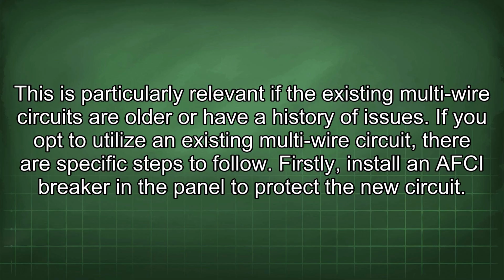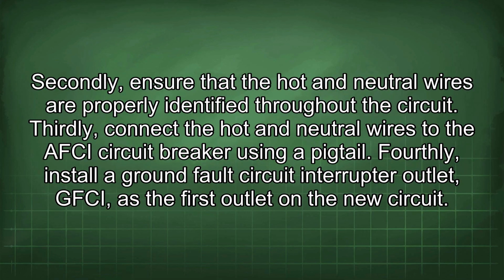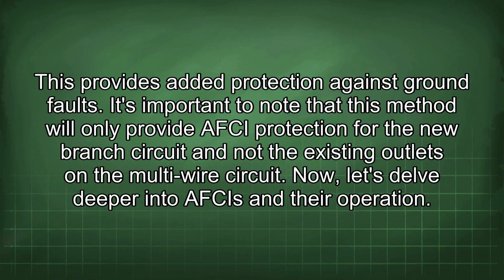If you opt to utilize an existing multi-wire circuit, there are specific steps to follow. Firstly, install an AFCI breaker in the panel to protect the new circuit. Secondly, ensure that the hot and neutral wires are properly identified throughout the circuit. Thirdly, connect the hot and neutral wires to the AFCI circuit breaker using a pigtail. Fourthly, install a ground fault circuit interrupter outlet, GFCI, as the first outlet on the new circuit. This provides added protection against ground faults.